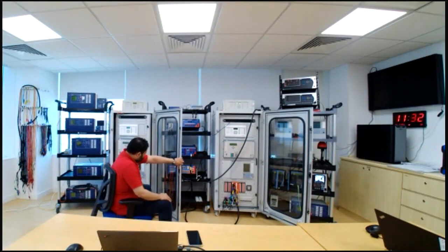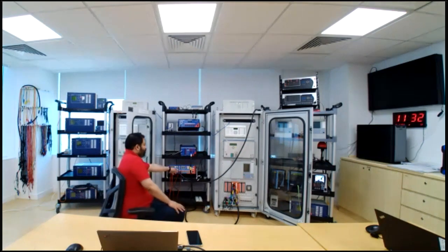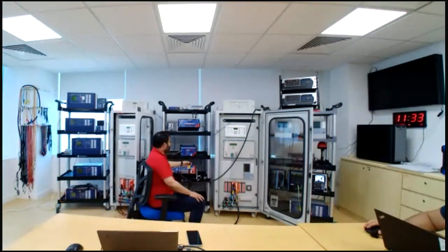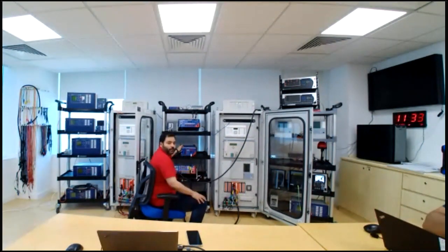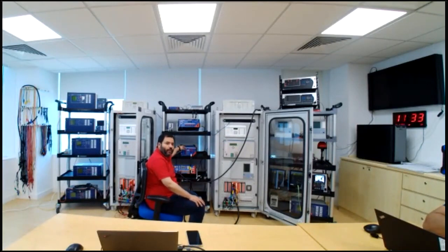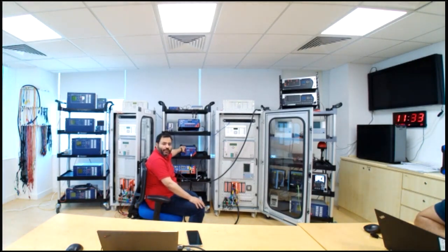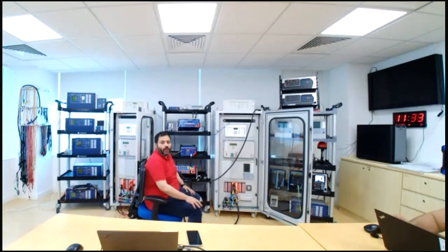You can see here the combined generator cable. I'm using it to take the phase voltage and three-phase current, getting the feedback to the CMC. Luckily, here I'm using IEC 61850 as GOOSE communication, the feedback from the relay to the CMC, to reduce the wiring effort. This is the new technology. Maybe very soon we will also have full digital substations in our countries. I know that it's already implemented in some countries, but not everywhere. Luckily, our CMC has been supporting full digital solutions for a long time.